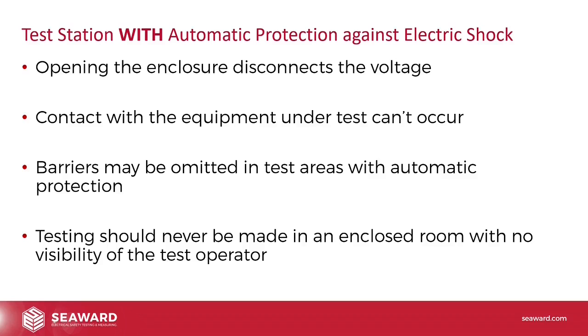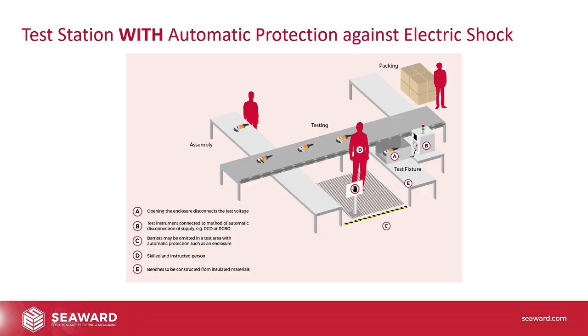Barriers may be omitted in this case when there's automatic protection, because it doesn't matter how close you get to that box, you can't touch the equipment while it's being tested. But again, testing should never be made in an enclosed room with no visibility of the test operator. So this is what that looks like. You can see it's a lot cleaner, a lot simpler. Yes, again, it's not ideal for everyone.